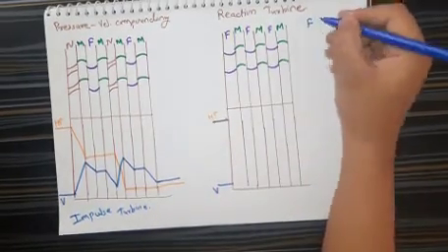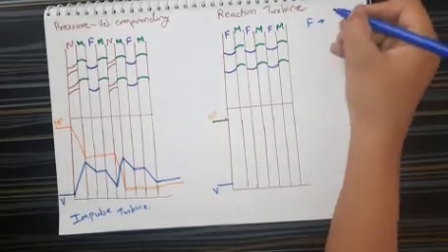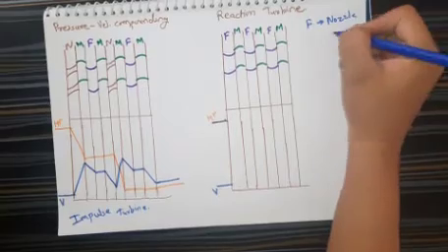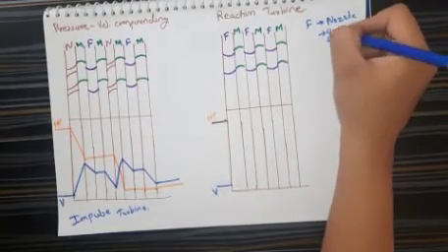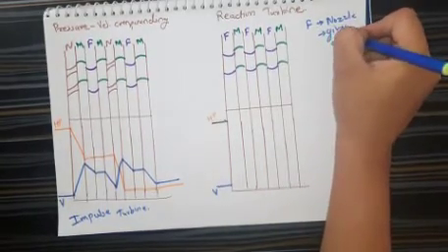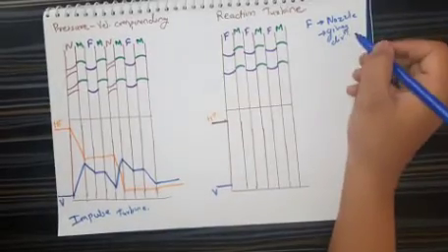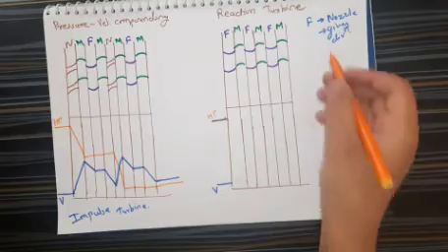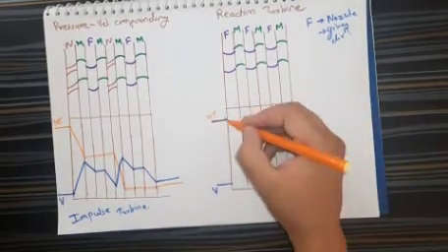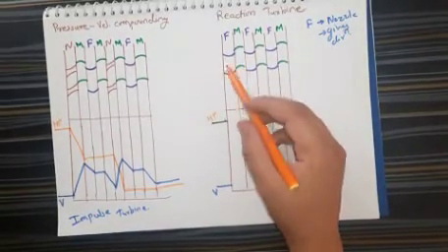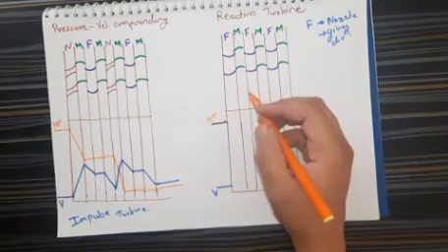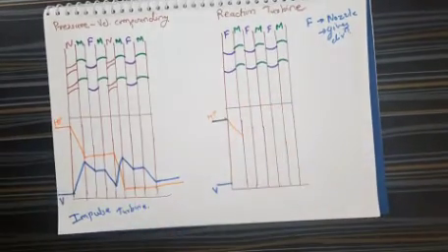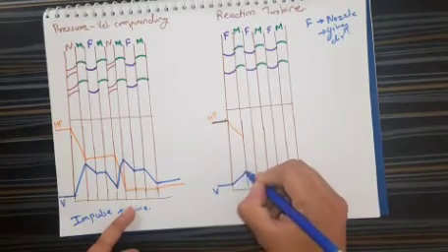In a fixed blade of this reaction turbine, it partially acts as a nozzle and also gives the direction to the steam. As it partially acts as a nozzle, the pressure energy in a fixed blade will drop down and it will be converted into kinetic energy.